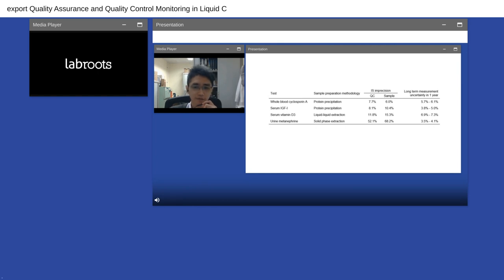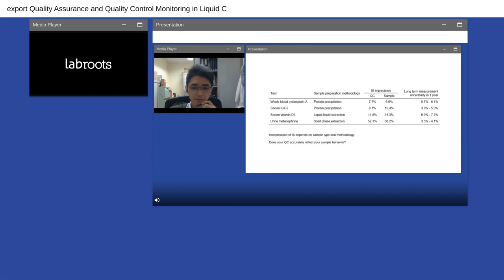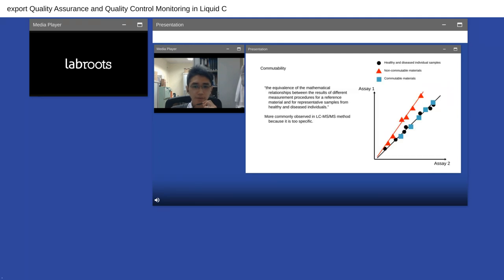Looking at long-term measurement uncertainty in different assays: even though IS dispersion can be large in some tests, the long-term measurement uncertainty is actually quite good — most below 8%, with comparable performance in EQA programs. This tells us the internal standard is doing its job, correcting for variation even when fluctuating at 60-70% CV. However, this practice relies solely on the commutability of QC material — the IS fluctuation in QC should mimic that of patient samples. This brings us to the next topic: commutability.